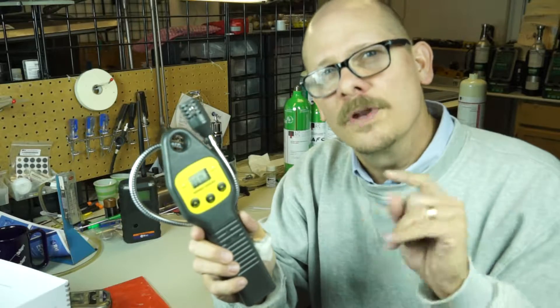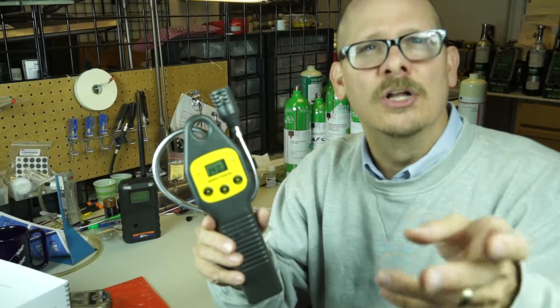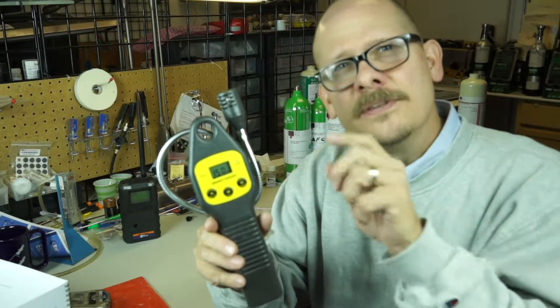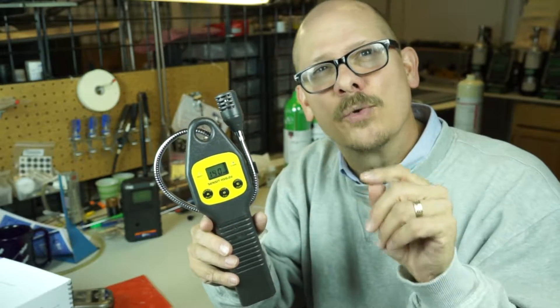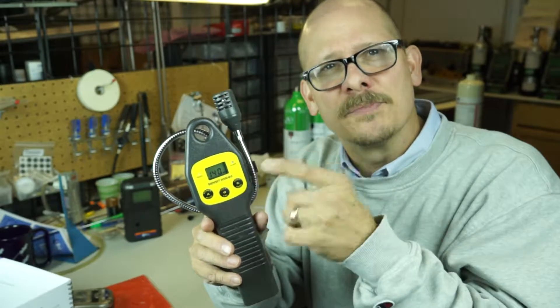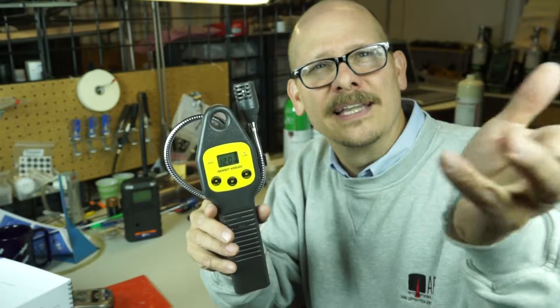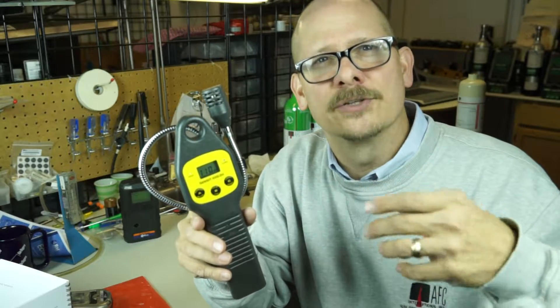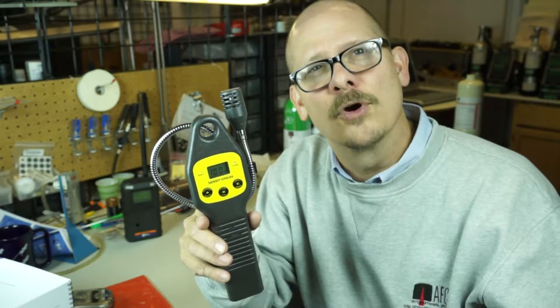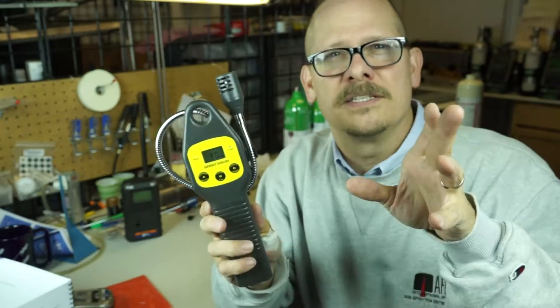One of the weaknesses of the HXG-2D I've found through the years is heavier hydrocarbons — gasoline, solvents, heavy liquid fuels. The MOS sensor in the instrument really wasn't designed for those types of gases and vapors. In fact, over time, those will burn that sensor out — actually very quickly. So I would use the HXG-2D from Sensit for methane and natural gas calls, propane gas calls for homes and residences, natural gas breaks, lines, and pipeline-type work. I would not use it as a poor man's photoionization detector or PID for hazmat applications — it just doesn't have the design for that. The intrinsic safety approval is also only for methane, propanes, butanes, and fuel gases for homes and heating.